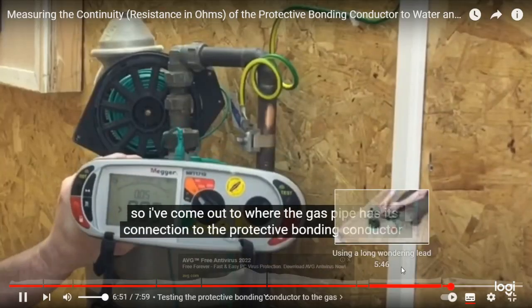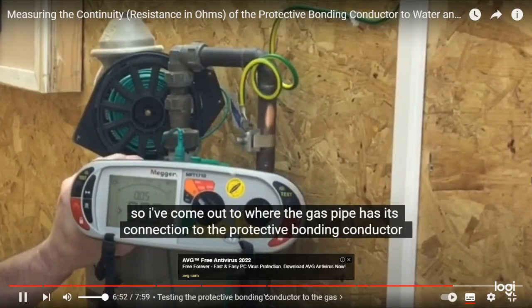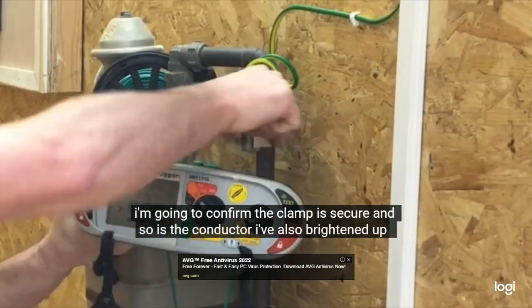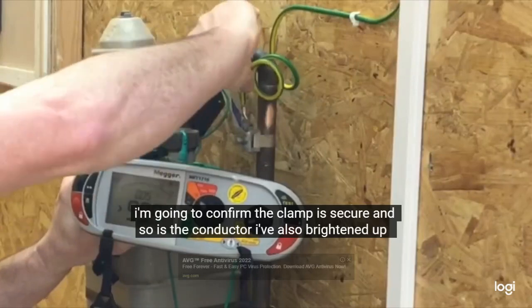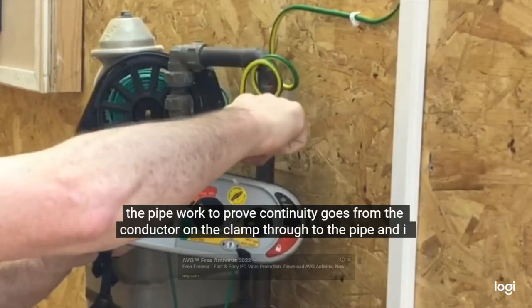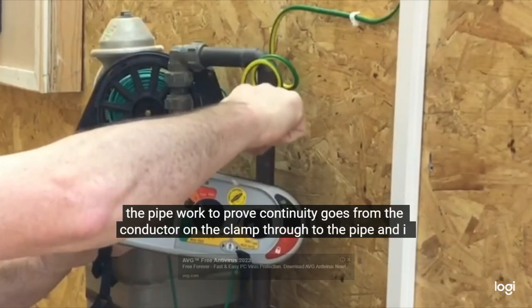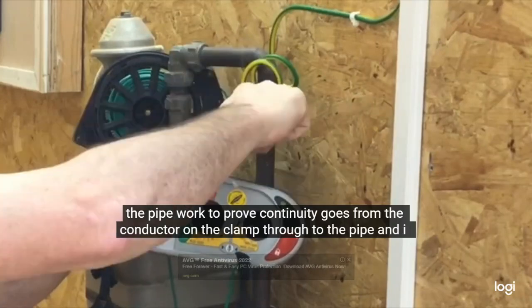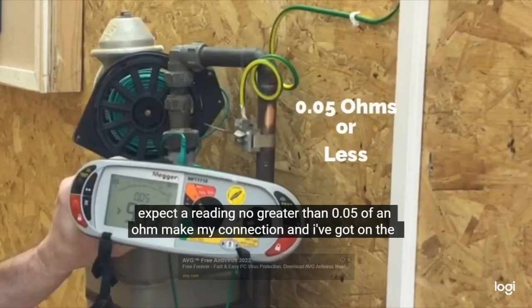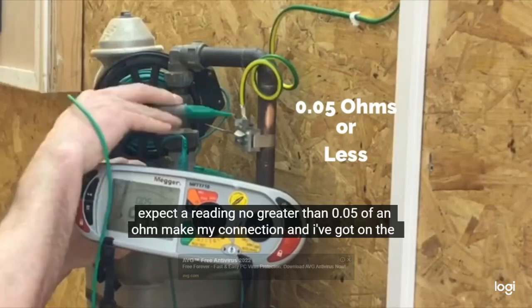So I've come out to where the gas pipe has its connection to the protective bonding conductor. I'm going to confirm the clamp is secure and so is the conductor. I've also brightened up the pipe work to prove continuity goes from the conductor on the clamp through to the pipe. And I expect a reading no greater than 0.05 of an ohm.